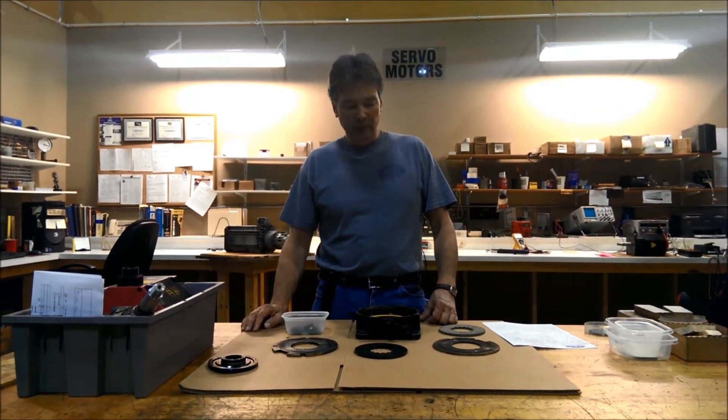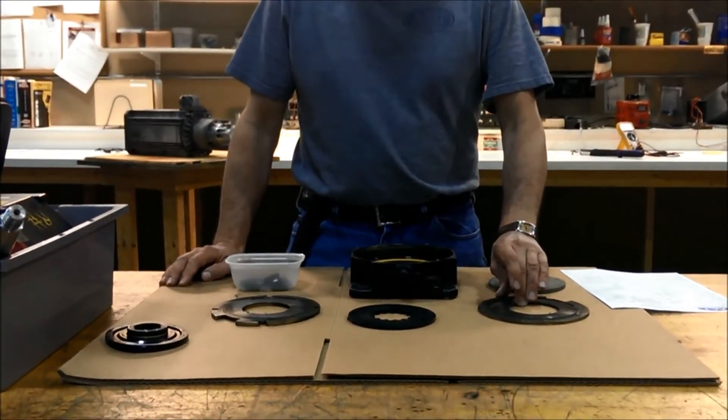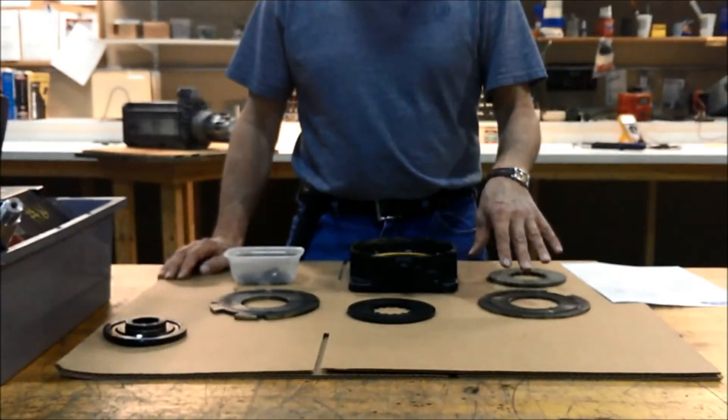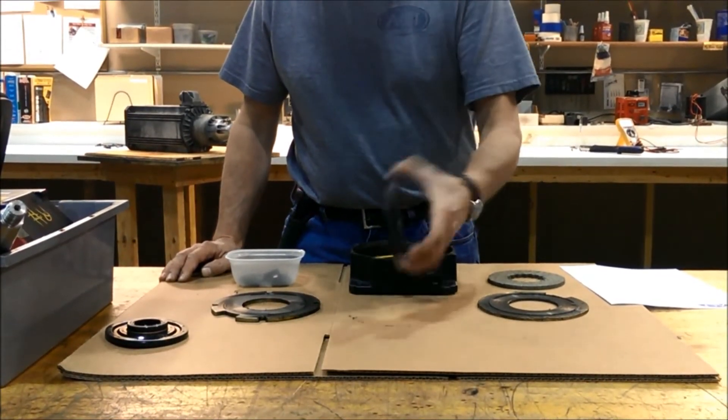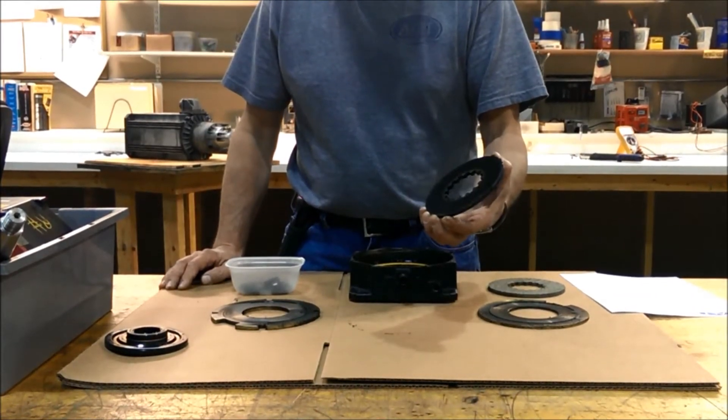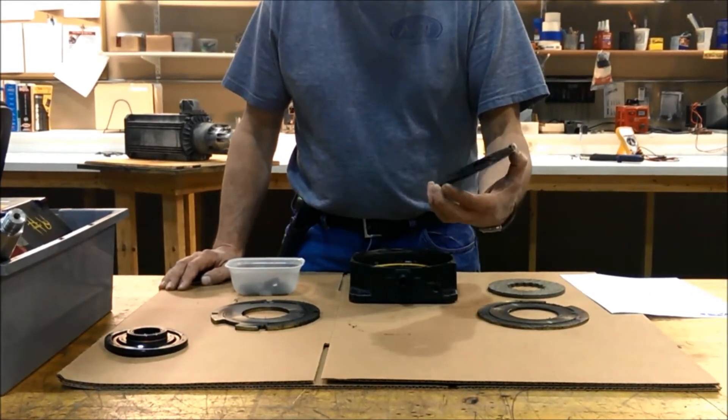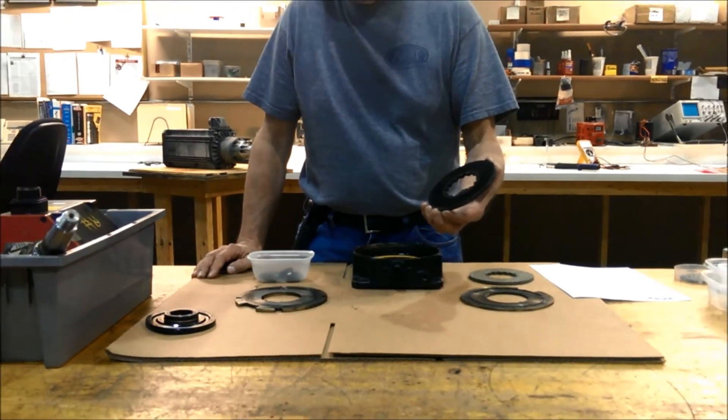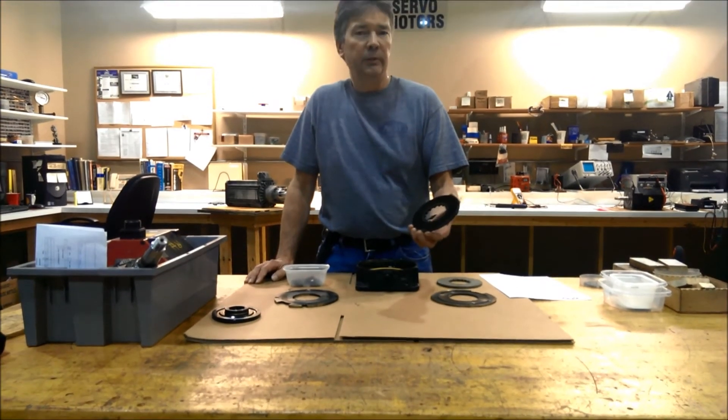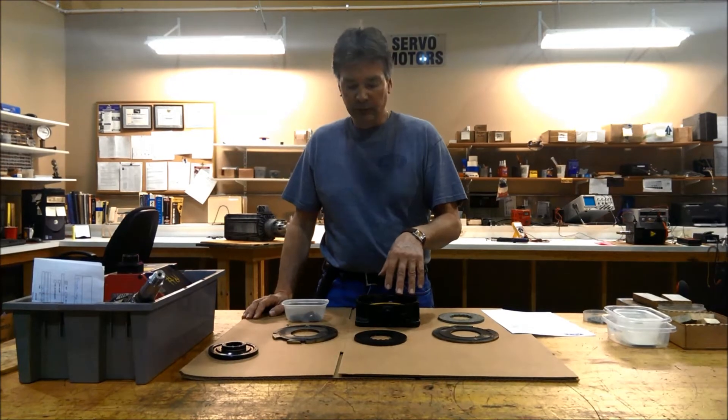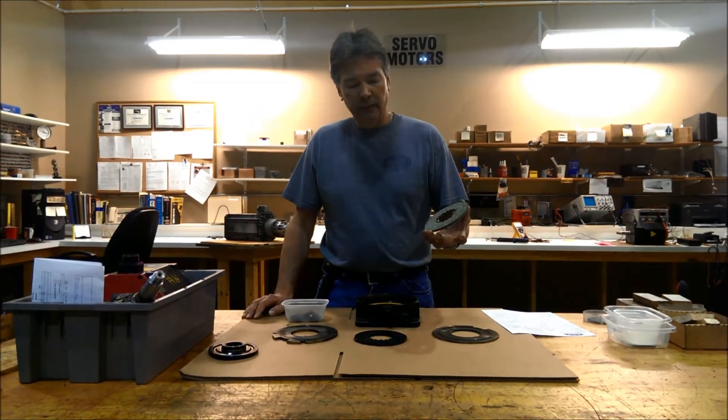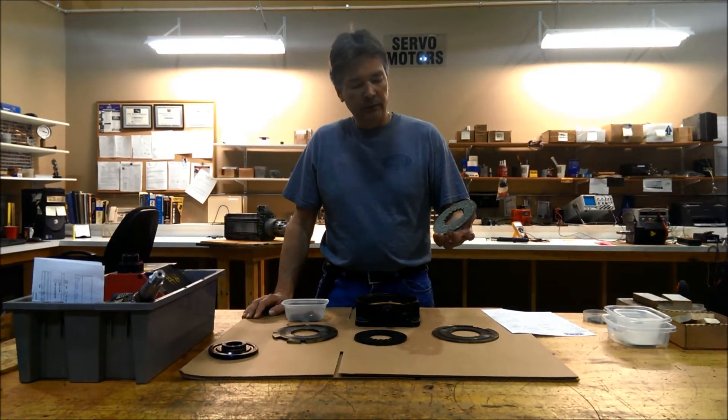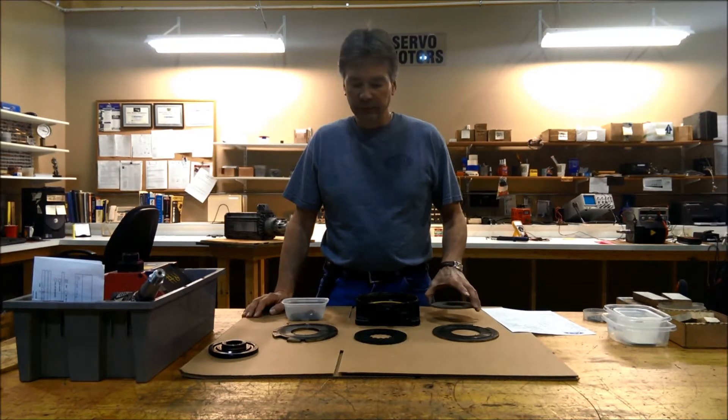What we have here are the various parts of the brake assembly. These are the discs here which we will clean of grease and brush up, and this is really the part that suffers the most from grease contamination. This is the brake disc assembly itself and it can become saturated with oil and grease. When that happens there's really no way to repair it, it has to be replaced. So we'll remove this one and replace it with a brand new pad, and that will help take care of the brake torque issues that we're seeing with these motors.